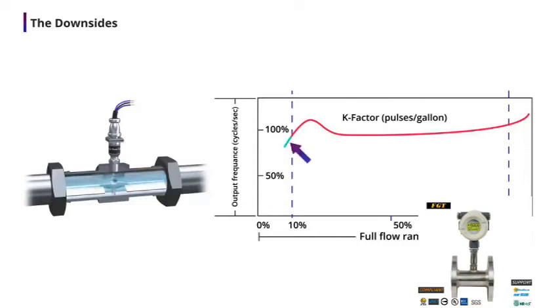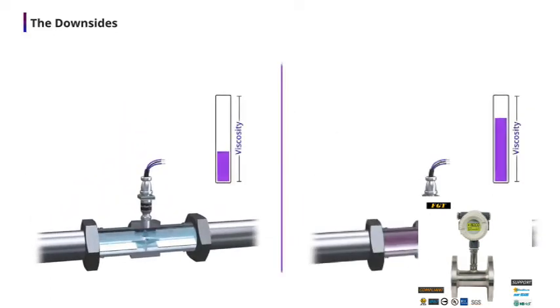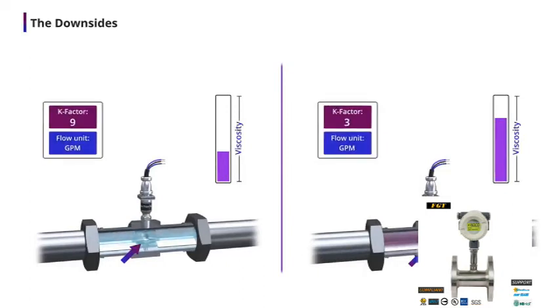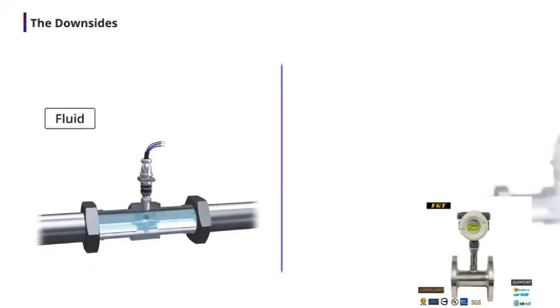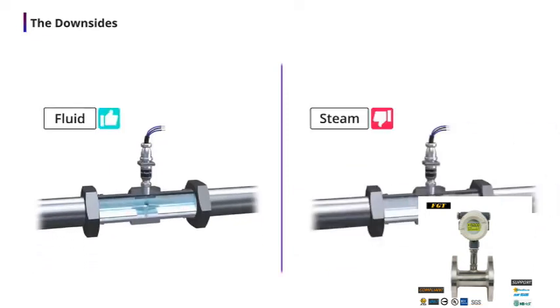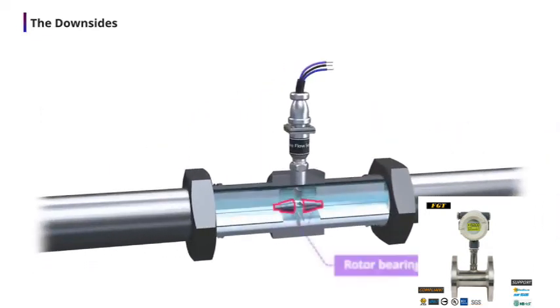Turbine flow meters are not accurate at very low flow rates. Viscosity is an issue, as thicker or thinner fluids can change the rotor speed and affect the meter's calibration. Keep in mind that the turbine flow meter K-factor was determined at the factory using a specific set of parameters. They are not recommended for steam. As with other mechanical devices, the rotor bearings wear out.